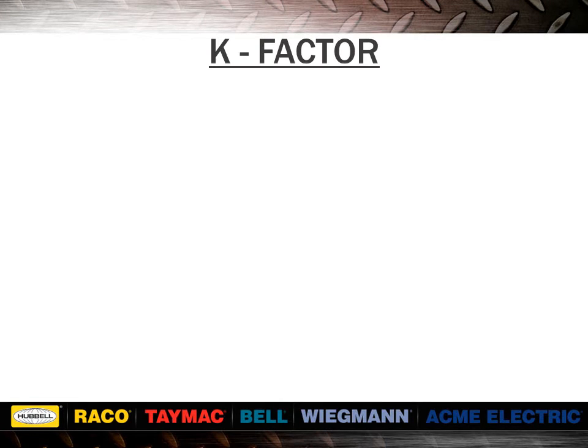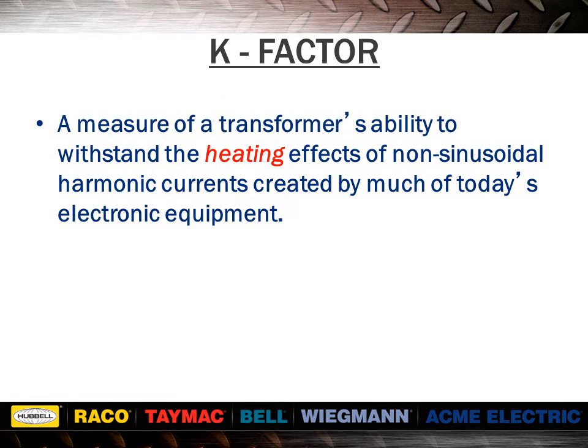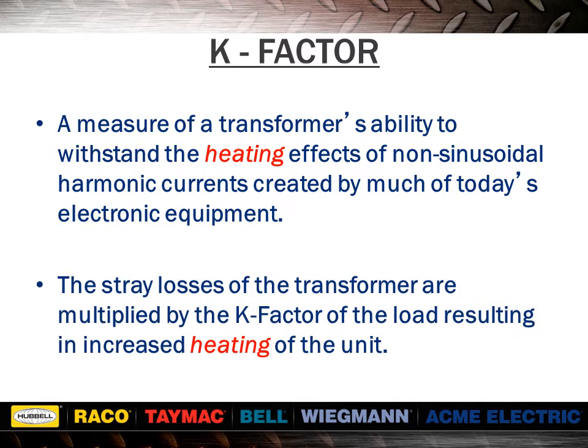The k-factor is a mathematical formula for calculating the heating effects of harmonics. It is a measure of a transformer's ability to withstand the heating effects of non-sinusoidal harmonic currents created by much of today's electronic equipment. The stray losses of the transformer are multiplied by the k-factor of the load, resulting in increased heating of the unit.